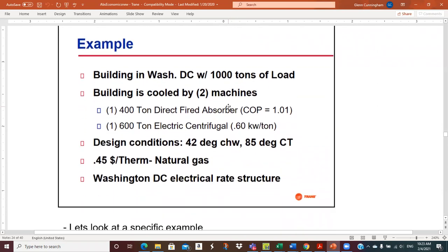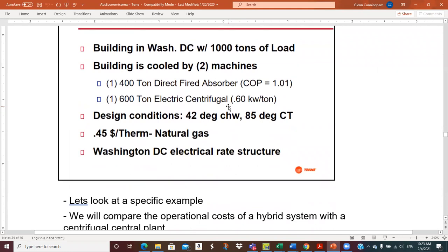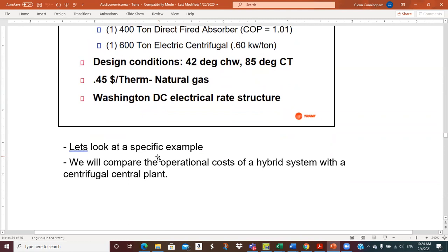All right, so now here's our example building. It's in Washington, D.C. We've got 1,000 tons of load. We're going to have 2 chillers in the building. We're going to have a 400-ton direct fired absorber, a COP of 1.01, and a 600-ton centrifugal electric that's 0.6 kW per ton. Design conditions are leaving chilled water temperature of 42 and entering condenser water, or cooling tower, temperature of 85, 45 cents a therm for gas, and it's the Washington, D.C. rate structure that we've already looked at.